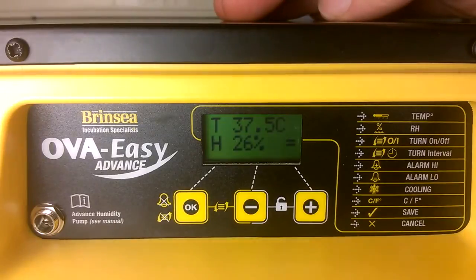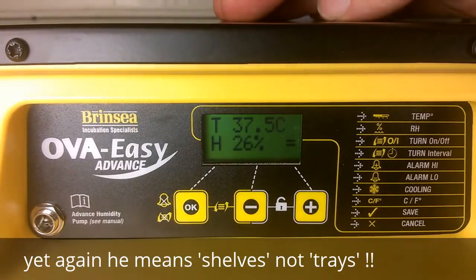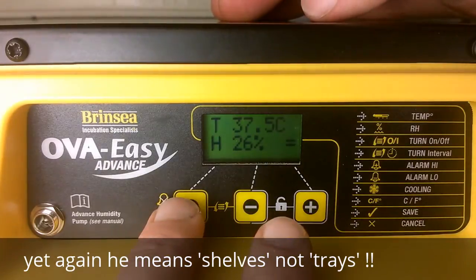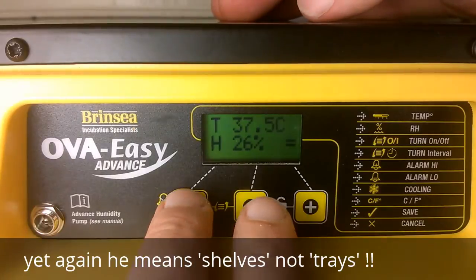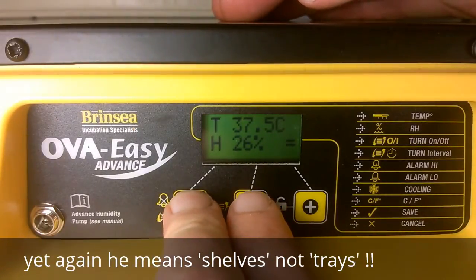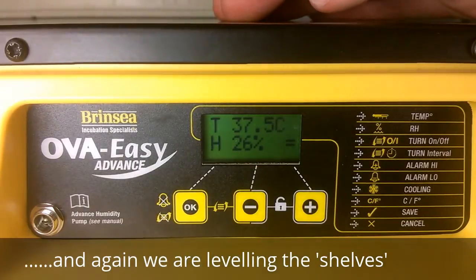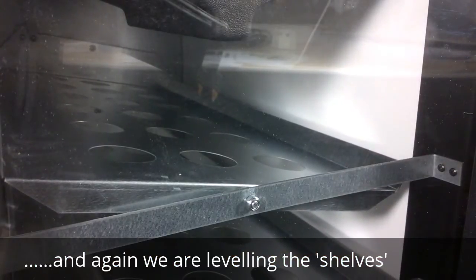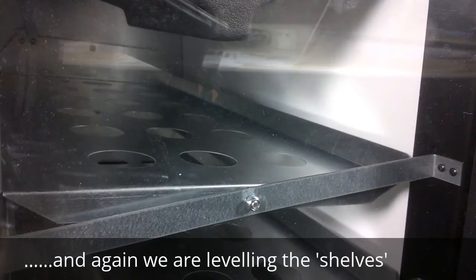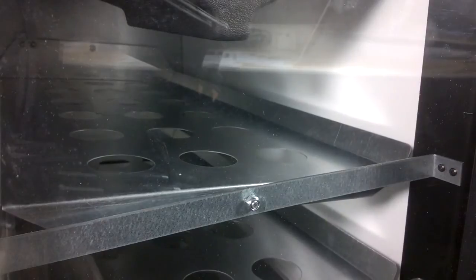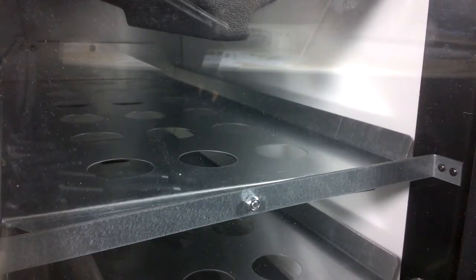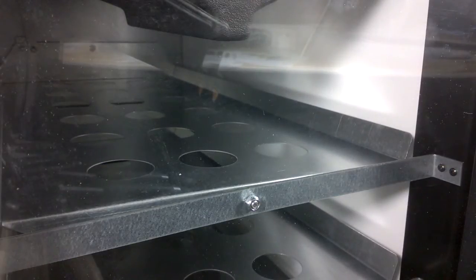When we've done that, we have now turned the turning off. What we now need to do is to bring the trays, which are still in a diagonal slanted position, into a level position. So all we do, having turned the turning off, is press the OK and the minus. You see the little turning sign there? The OK and the minus brings the trays into a level position. You hear the buzzer sound. That is now activating the turning of the trays so that they come into a level position, and then the turning will stay off. So the trays, as you can see, having done that exercise, are now coming into a level position. There we go, they're level now.